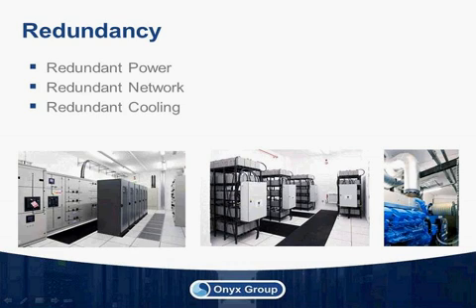I mentioned the term N+1 earlier on. I'll explain what this means. For example, if the load can be supplied by 3 UPSs, then the setup will include 1 more UPS in case one fails, so it takes out the single point of failure. Another less common configuration is what we call 2N. So this would be, for every UPS, there would be another UPS, which is considered overkill.